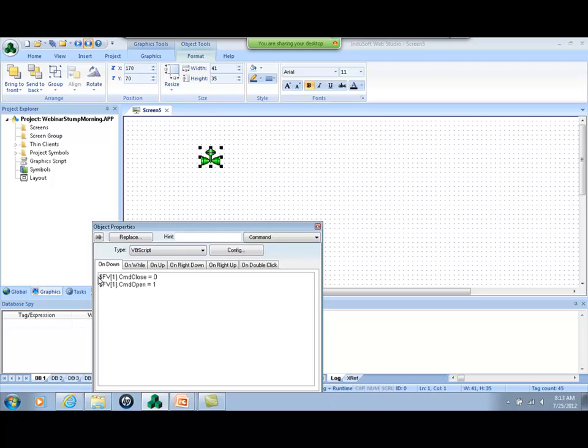So right here, instead of just defining fv command close, I can assign an alias for this tag, for this property. And the syntax for that is hash pound sign, the name of the alias, like fv colon, and the default value. So the default value here happens to be the valve 1. But since I'm linking those values to a custom property called fv, I'll be able to customize those tags for each instance of the valve.